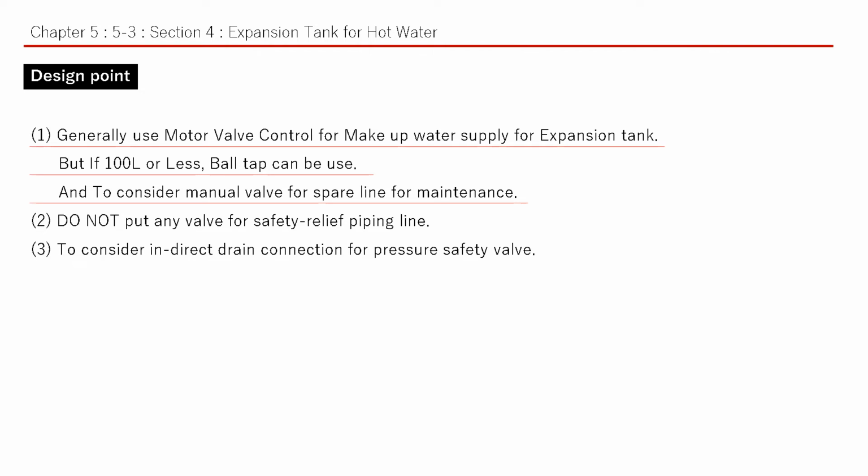Design point, 1, generally use motor valve control for makeup water supply for expansion tank. But if 100 liter or less, ball tap can be used. And to consider manual valve for spare line for maintenance. 2. Do not put any valve for safety relief piping line. 3. To consider indirect drain connection for pressure safety valve.